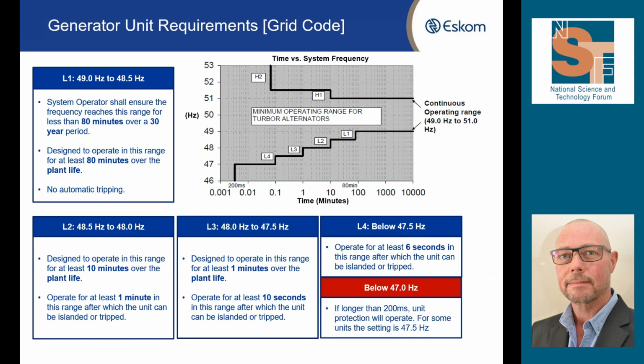As we go further down in frequency, at 48 hertz, over the lifetime of the plant they would expect to be operating there for only about 1 minute, and they would then start tripping within seconds should we get down to those frequencies. And then below that, it really gets chaotic. We're talking about 6 seconds, and below 47 hertz, we're talking about 200 milliseconds towards tripping.